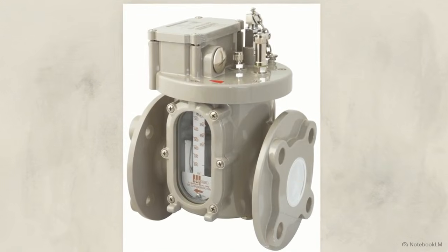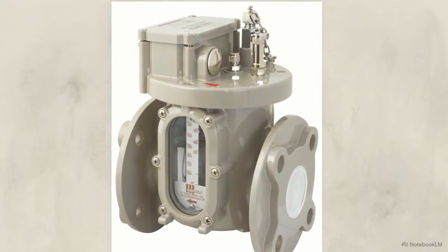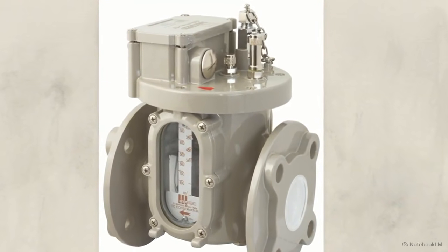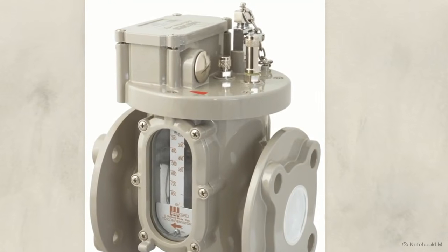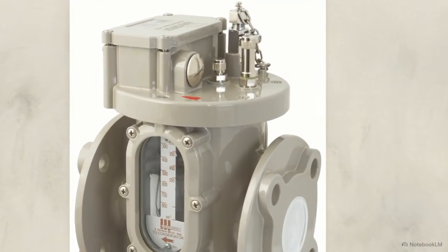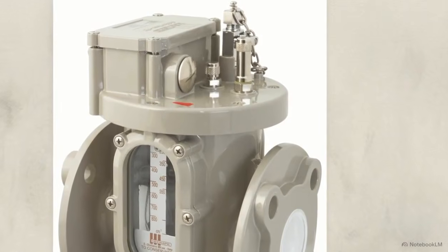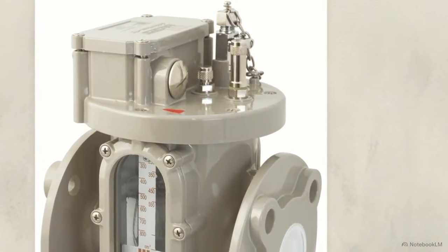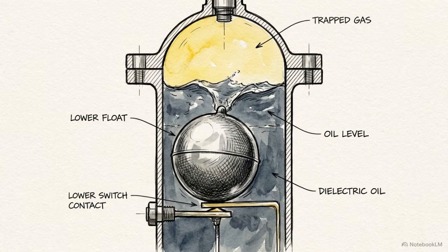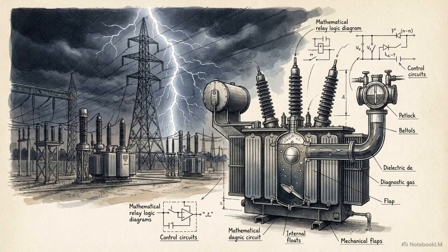Once safely offline, diagnostics begin. Engineers use the petcock valves on top of the relay to extract trapped gas. Visual checks reveal the fault: whitish for paper arcing, yellowish for wood degradation, grayish for core breakdown, and black for severe free arcing. The elegant dual float mechanics of the Buchholz relay perfectly translate invisible chemical deterioration into direct, actionable mechanical data. However, the Buchholz relay has one major limitation. Because it only detects internal chemistry, it is completely useless against massive external grid faults.